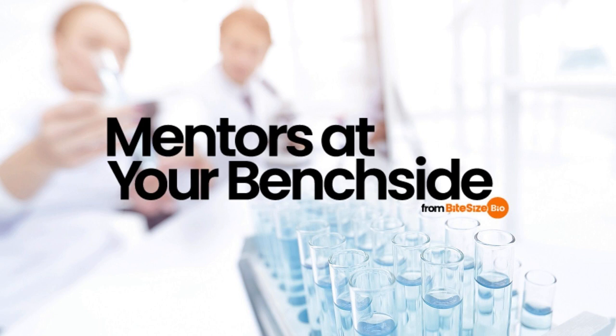Here you take 2 samples, each with a weight of half the weighing capacity of the scales. Add sample 1 to the scales and note the value, then zero the scales, and add sample 2, note the value, and add sample 1 alongside sample 2. If the value changes outside of the acceptable range, again, it is time to calibrate.